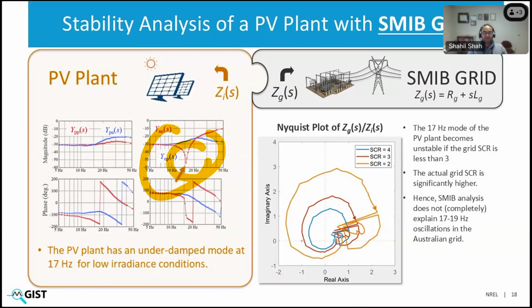Anyways, I think I can do with this. So we find an underdamped mode for low irradiance condition. Now, once you have this impedance scan, which shows that there is an underdamped mode, within a second you can determine if it is stable for a particular short circuit ratio or not.